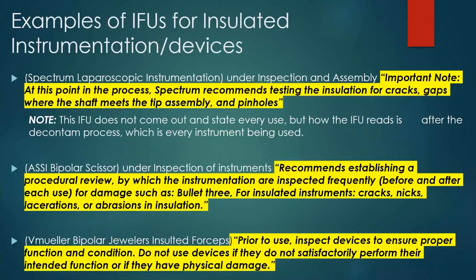The first one was spectrum laparoscopic instrumentation. It says: important note, at this point in the process, Spectrum recommends testing the insulation for cracks, gaps where the shaft meets the tip assembly, and pinholes. I put a note here that this IFU does not come out and state every use, but the way it reads is basically after the decontam process, which is basically every instrument used. But again, I encourage everyone to go back and look at the whole IFU for these devices.